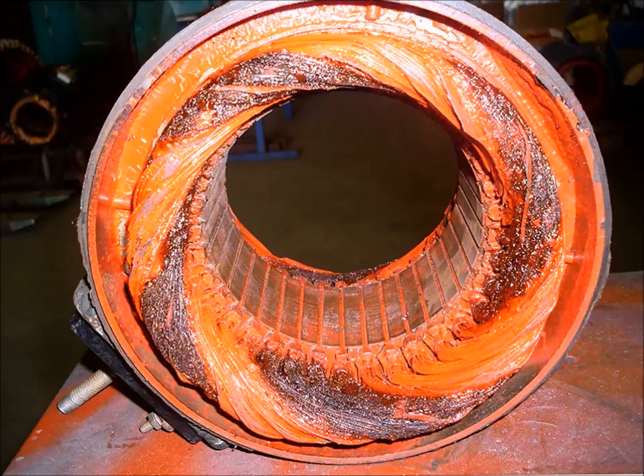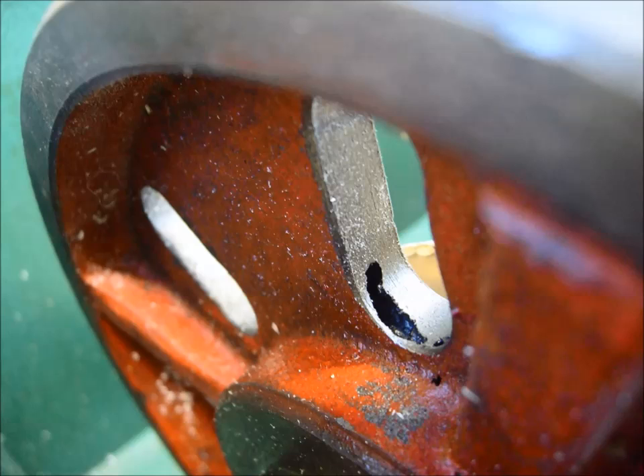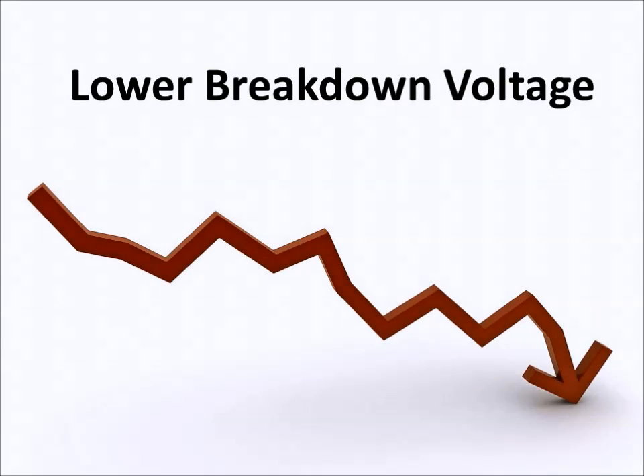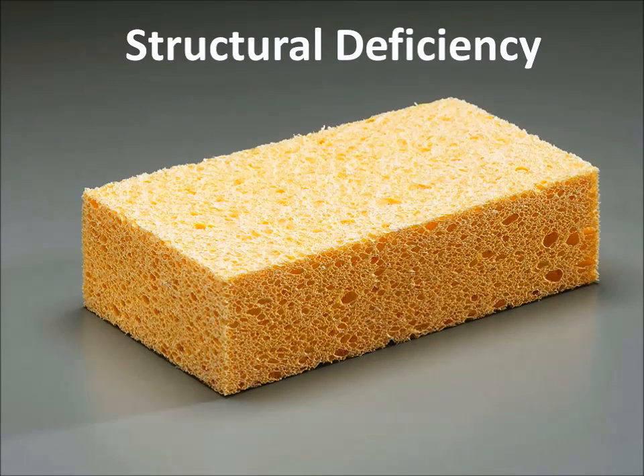Physical voids in the insulation material ultimately exist between the wires, leaving it susceptible to external influences such as moisture. If the gaps are left untreated, the finished products will suffer subpar performance and lessened longevity. These gaps may cause a variety of issues related to temperature, structure, and efficiency. Gaps and voids provide a low-resistant path for electric charges, thus lowering the breakdown voltage of the insulation system. Partial discharges may occur, causing progressive deterioration of insulation materials. This will eventually lead to electrical breakdown and in high voltage instances can be very dangerous. Structural stability becomes an issue, as these gaps result in a weak sponge-like construct which is susceptible to fail under pressure caused by vibration or expansion and contraction.